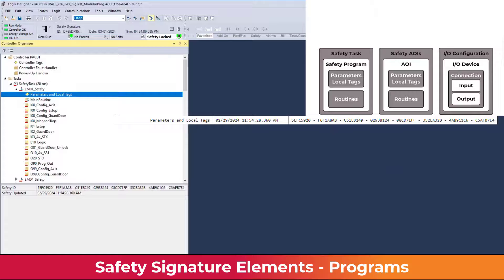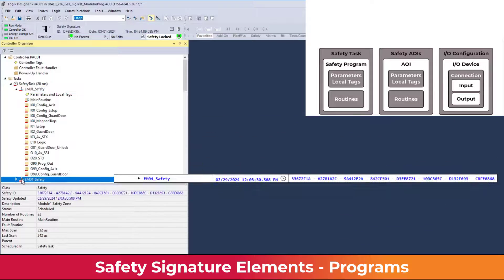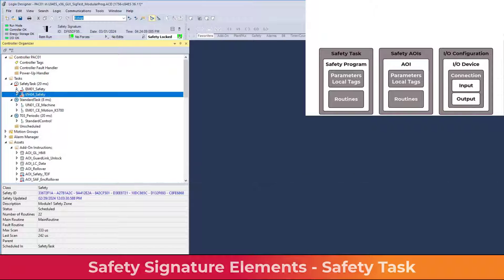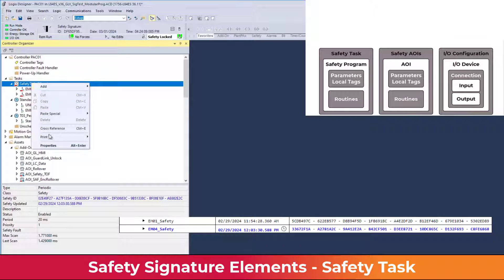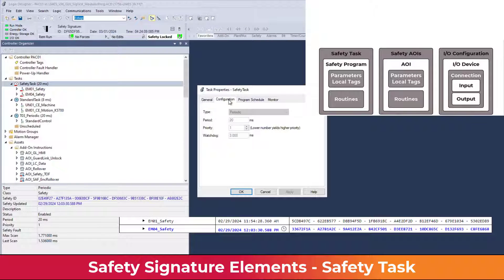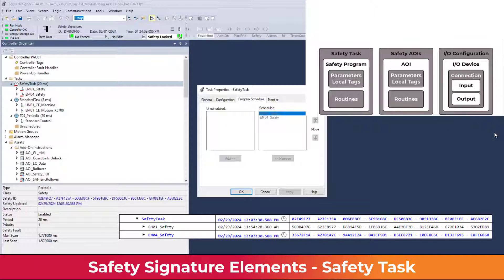Safety critical values should be stored as constants or written using logic in the safety task. The safety program's signature is made up of all routines and the parameters and local tags. There is a safety signature for each safety program, and the safety signatures of each program combine with the safety task configuration and program schedule to make up the safety task signature.